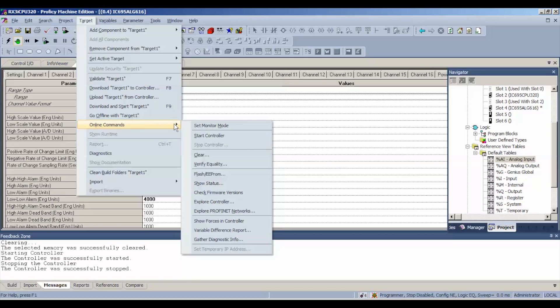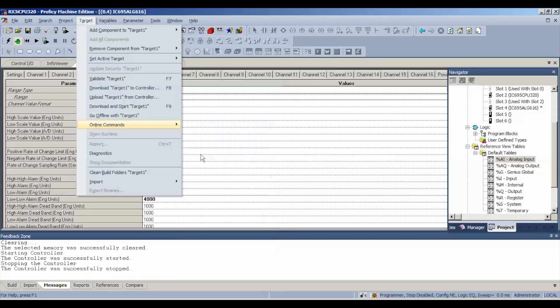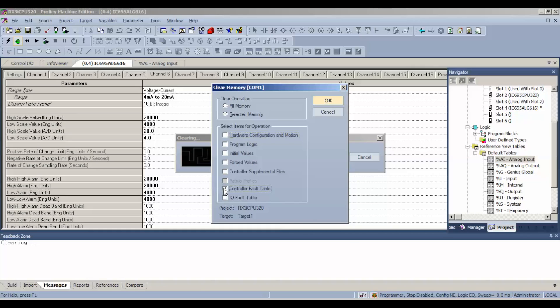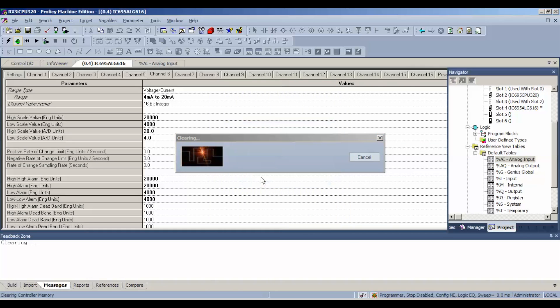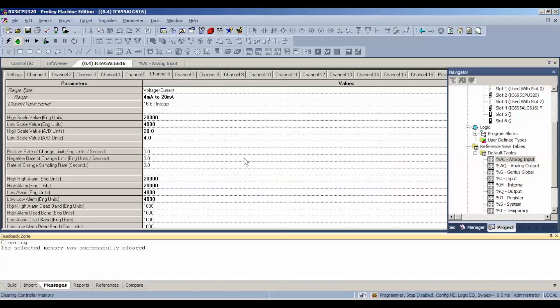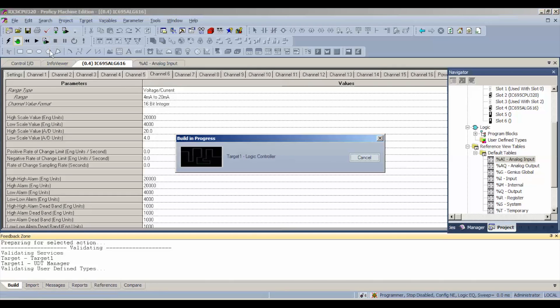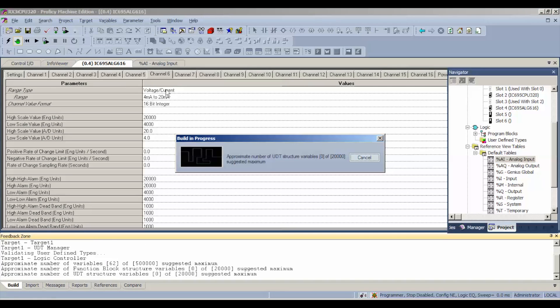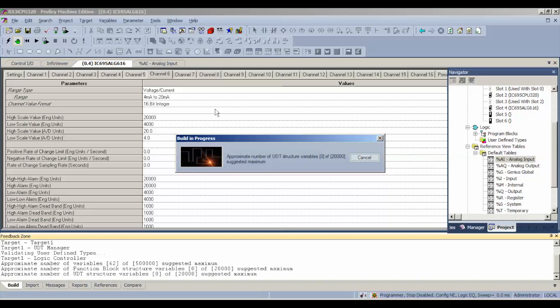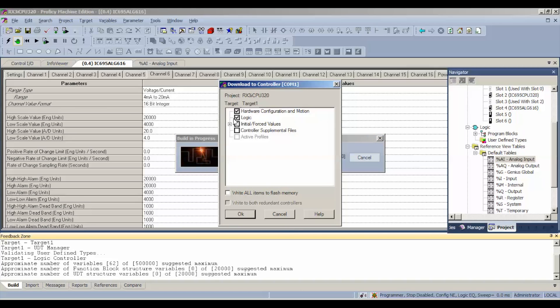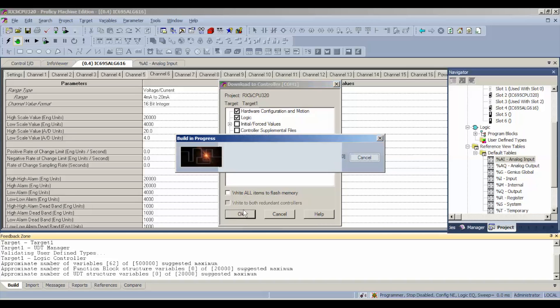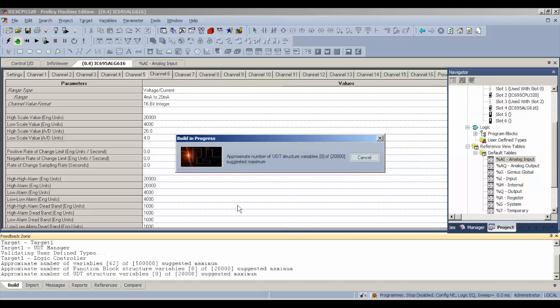Go to online commands through the target bar, clear, and we want to clear controller and IO fault table. Again, make sure you do that or you're going to get hung up when we do the download and start active target, which we're doing now. Same thing as before. When it asks us what do we want to download to the controller, just hardware configuration and motion and logic. We'll keep it really simple, simple as possible. You're just probing the inputs to make sure that the card works. Top two selections. Yes.